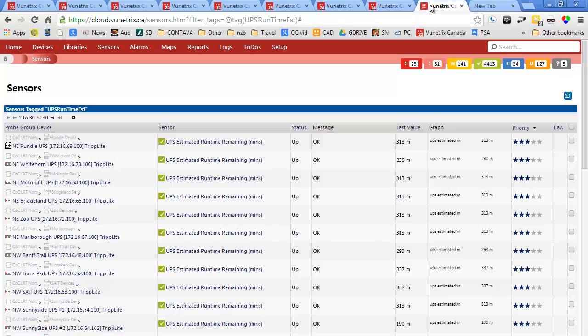In addition, the performance of the UPS is going to degrade over time as the batteries age, and you're going to see that as well. You'll be able to see a graph over time and trend off of it to see when the runtime values are going to cross a threshold that's important to you. So if it's 60 minutes, and that looks like it's going to happen in about a year's time, now you can start having that conversation with the customer about budgeting to do the maintenance on those UPS.